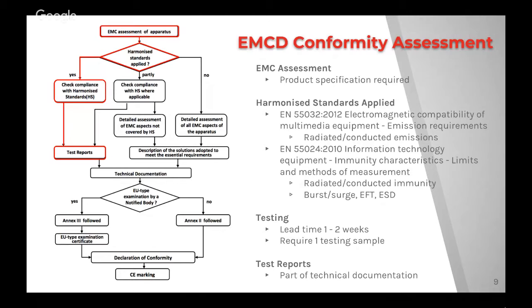Testing for EMC generally takes 1 to 2 weeks and can vary slightly depending on the product complexity, and normally will require one testing sample. That's to check the compliance with the harmonized standard. And lastly, test reports become part of the technical documentation that the manufacturer needs to compile and maintain.